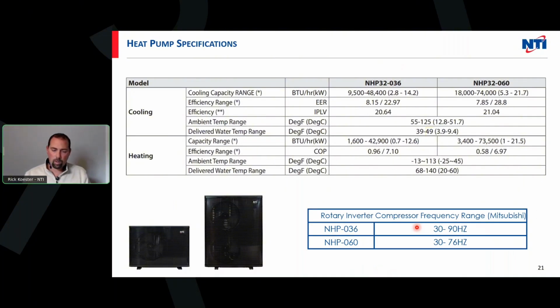If you're familiar with heat pump design, it's given us the ability to size smaller on the indirect tank, which has been the buffer tank, which has given us the ability to capitalize on some space in a mechanical room possibly. And we could talk more about buffer tanks shortly.